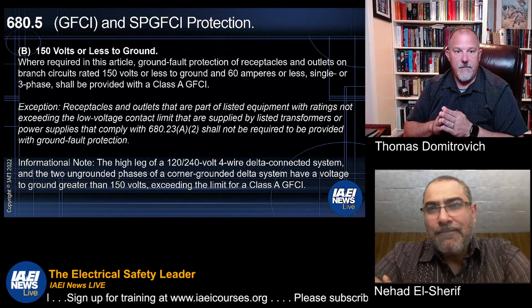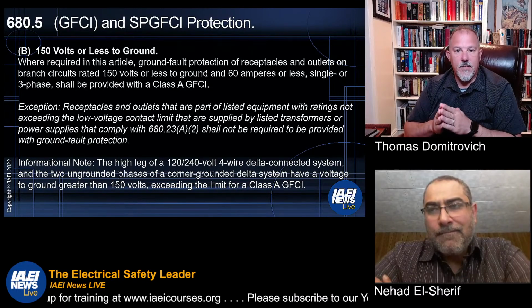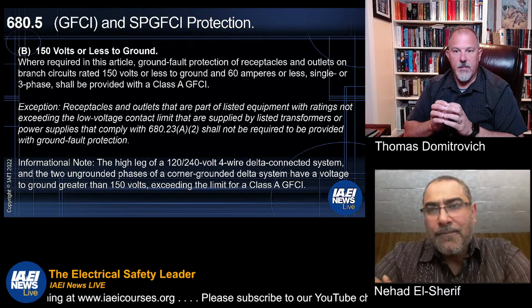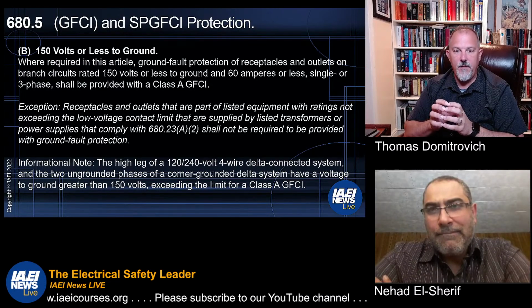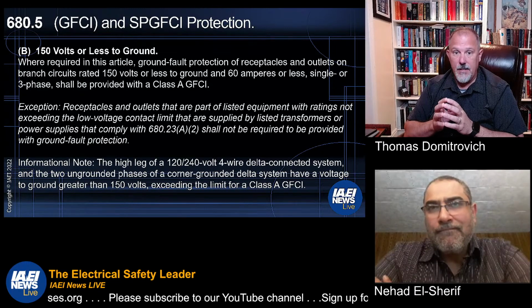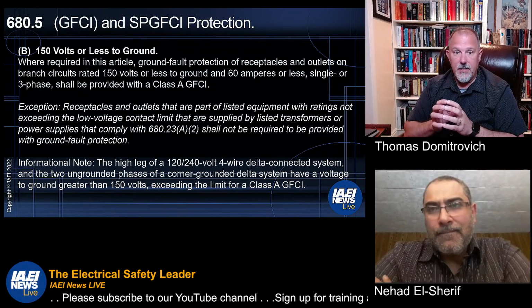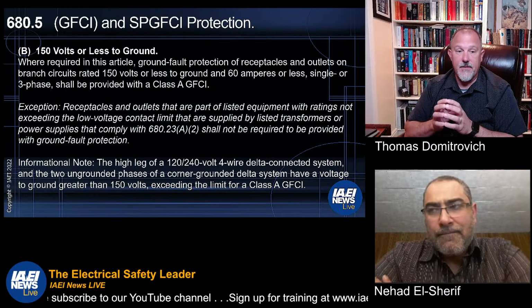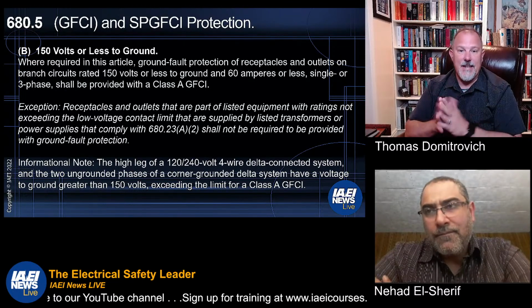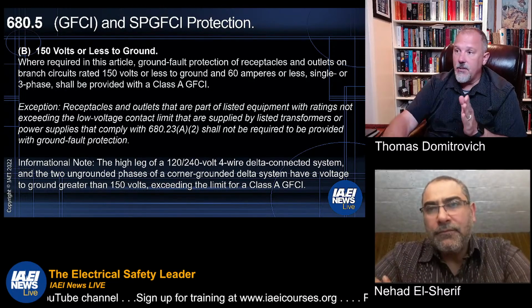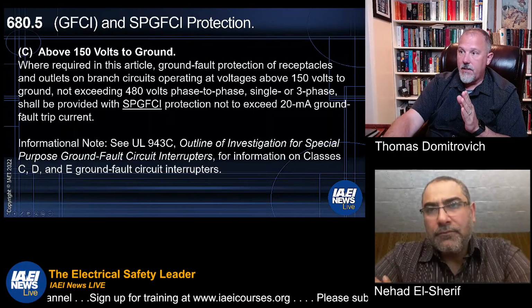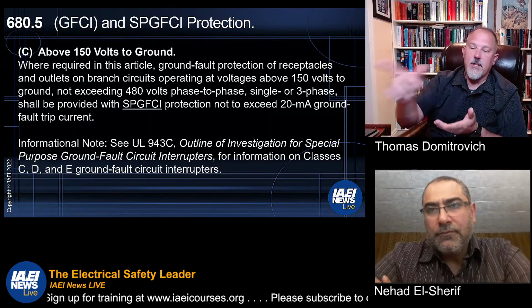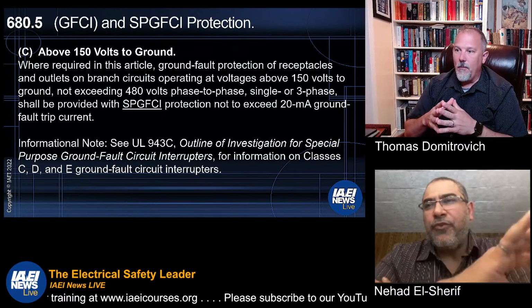680.5(B) says, where required in this article, ground fault protection of receptacles and outlets on branch circuits rated 150 volts or less to ground and 60 amps or less shall be provided with a Class A GFCI. No, I'm good with that. That's a Class A. Okay, so that's your GFCI. Now, (C) is above 150 volts. All right, that's perfect.